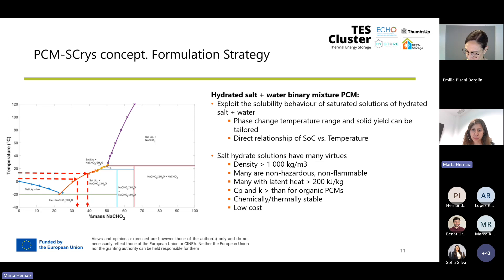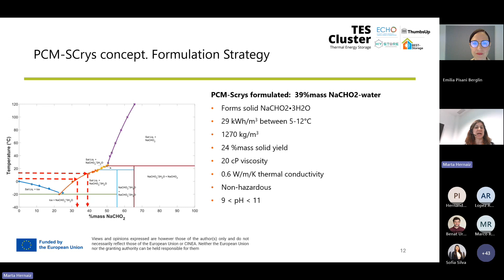Up to now, we have selected a slurry based on sodium formate, 39% in weight in water. This material has an energy density of 29 kilowatt hours per cubic meter, which means five times higher density than the reference material, which is water. Also, we have good thermal conductivity, very low viscosity, and we are handling a non-hazardous material in the pH range between 9 and 11.